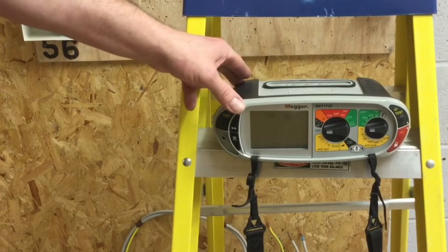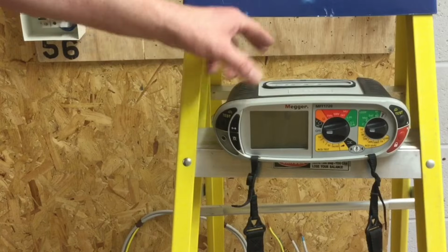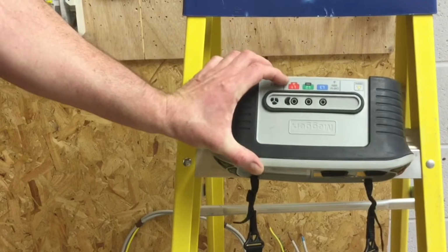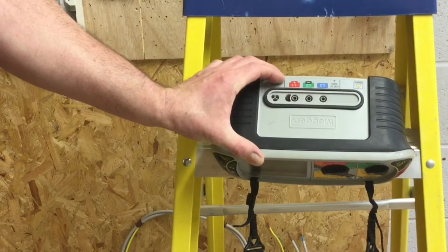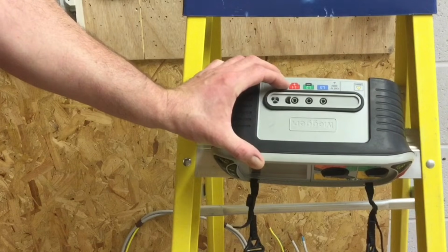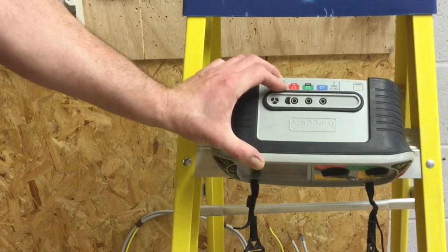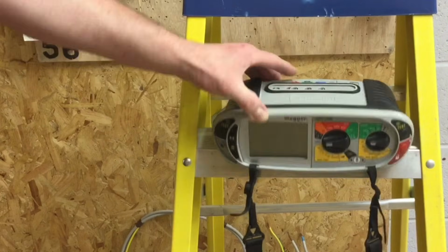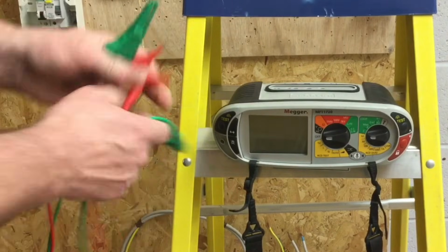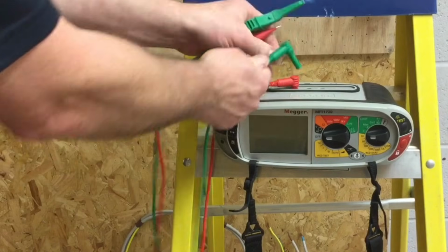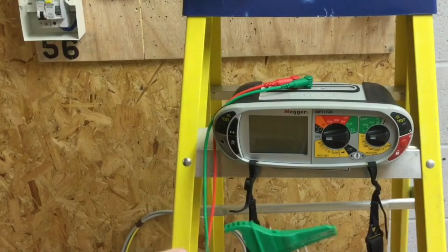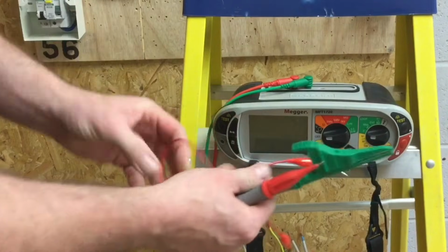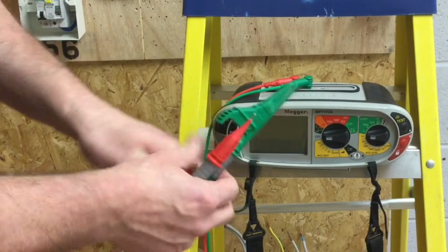We're using the Megger MFT tester, and in order to do a continuity test you must use the red and green located holes in the top. It wouldn't matter if I used the blue lead, but I've still got to use L1 and L2, which are represented by red and green. So I am going to use my red and green leads. So in we go. And because the leads themselves are also made of copper, as is our link, we're going to need to remove the resistance of these during this test.